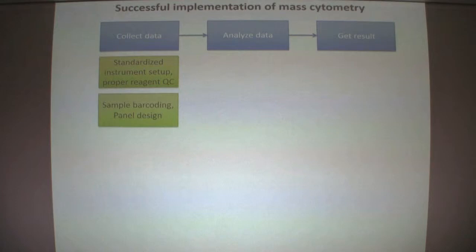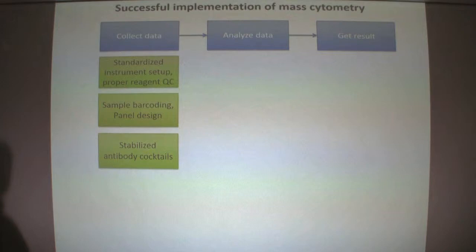We dealt a lot with generating tools and helping the data quality of mass cytometry. Things to keep in mind to make data very consistent include: standardized instrument setup and reagent quality control, sample barcoding to minimize technical error, stabilization of antibody cocktails — something used in flow cytometry but not yet in mass cytometry until we found a solution — and the use of reference beads and cell samples for tracking the performance of mass cytometry experiments and studies.